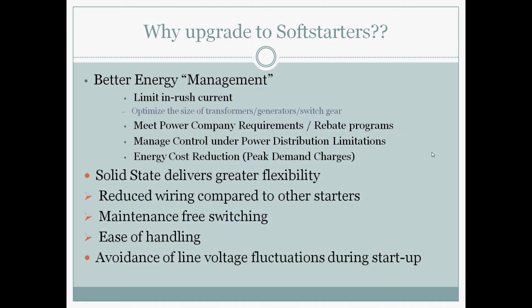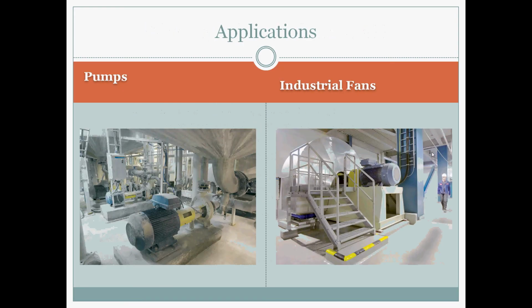Now why upgrade to soft starters? Better energy management, definitely. No surge is observed here, right? Limit inrush current, optimize the size of transformers, generators and switchgear, meet power company requirements, rebate programs, manage control under power distribution limitation, and energy cost reduction with peak demand charges. Solid state delivers greater flexibility. It is a very key feature of a solid state device, providing greater flexibility in comparison to bulky electrical devices. Reduced wiring compared to the other starters. Maintenance free switching. There is no huge amount of maintenance required because it is mostly an electronic circuit. Ease of handling. Avoids line voltage fluctuation during startup.